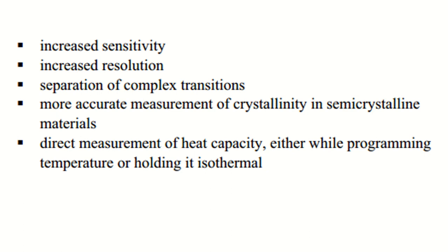In modulated DSC, there is a quite significant advantage over traditional DSC, because it measures both the heat capacity component and the total, and the kinetic component from the difference. That helps give more advanced information about that particular compound.